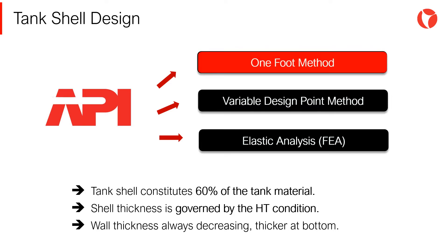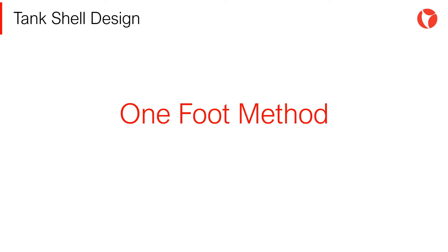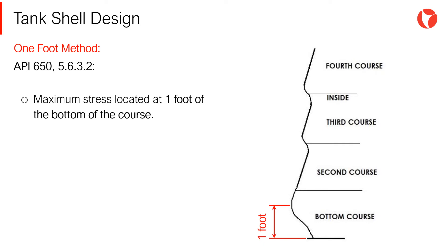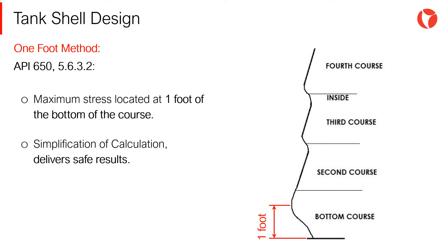From all these three methods, we will study the 1-foot method in this module. The 1-foot method is the most widely used, mainly due to its simplicity and due to the fact that the results are on the safe side. This method determines the shell thickness, considering that the design point for each course is located at 1 foot above the base of the shell course. This simplification in the calculation process is on the safe side. The 1-foot method cannot be used for tanks with diameters larger than 61 meters.